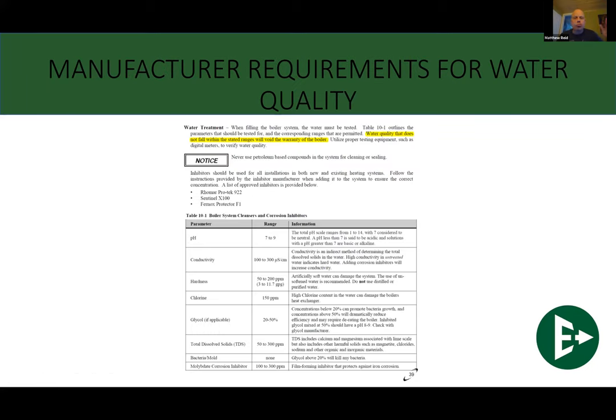Now, we don't want to go down way too low. You don't need to. When you go down too low by doing a demineralization, by dropping your total dissolved solids too low, you can create what's called hungry water. Again, Mother Nature loves balance. This water is used to having some sorts of minerals in it. If you take it all out, it's going to pull those minerals back in from anywhere it possibly can. We're talking about it'll strip away the inside of copper, the inside of ferrous metal. It'll pull all of that inside of it. So it'll do as much damage as it can by pulling these other ions from other areas.